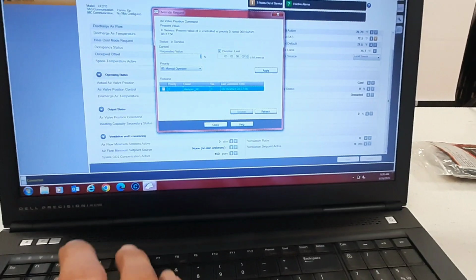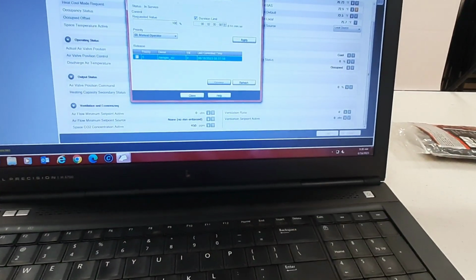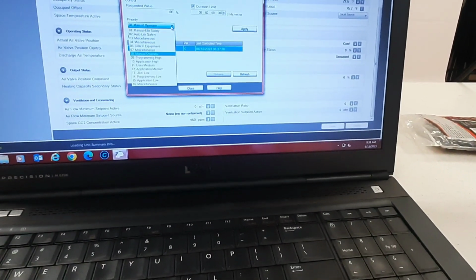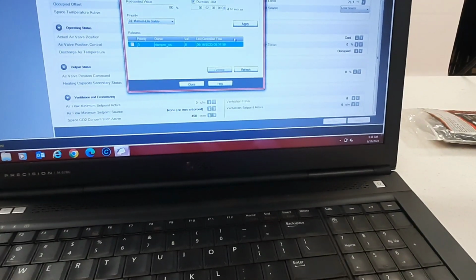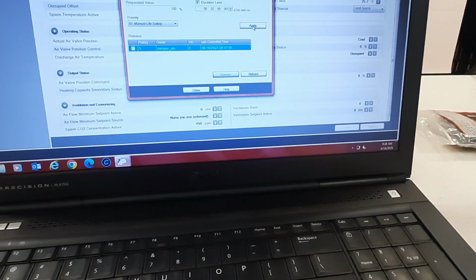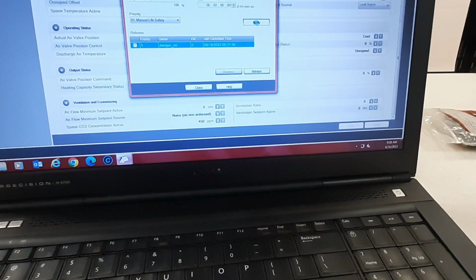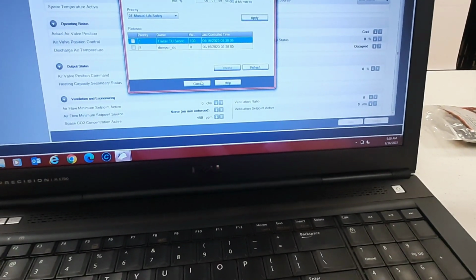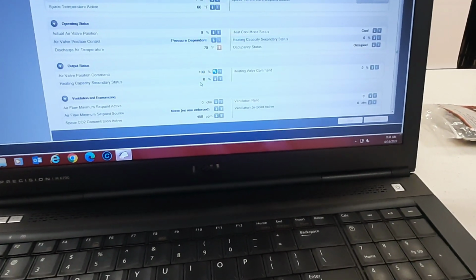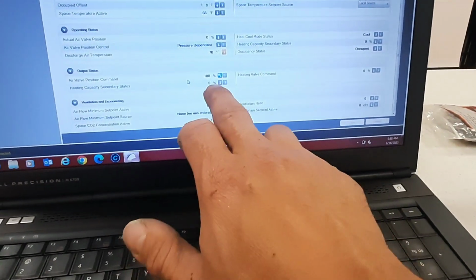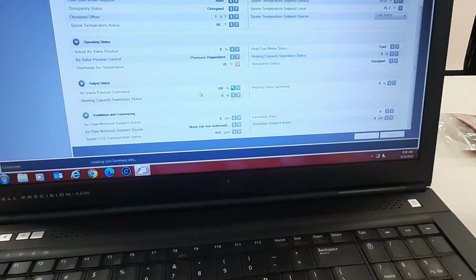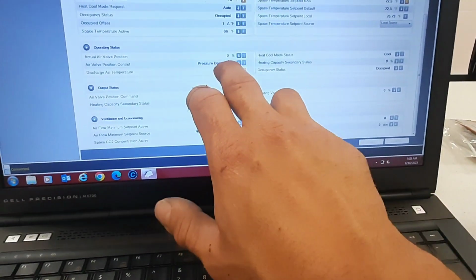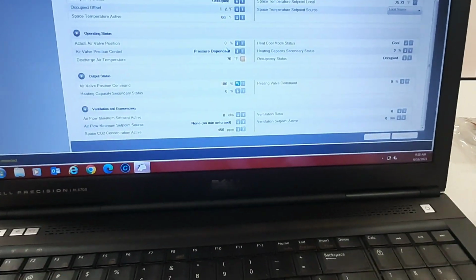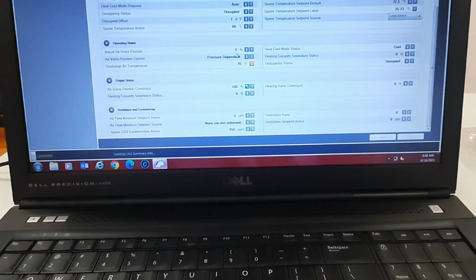Let's try one more time. Let's do it like this. 100. Let's go to manual life safety. Maybe that's why it's not taking. If you don't have a priority level over the damper control, it may not take. There it goes. 100%. This is my actual air valve position, and it should start driving open.